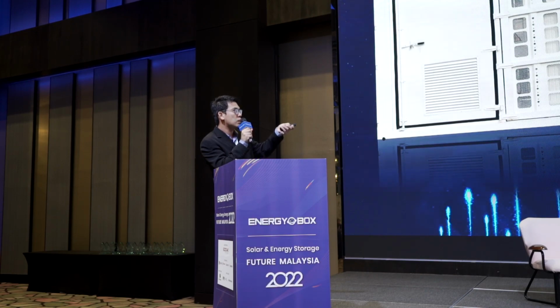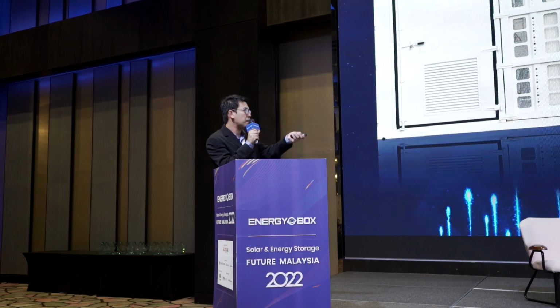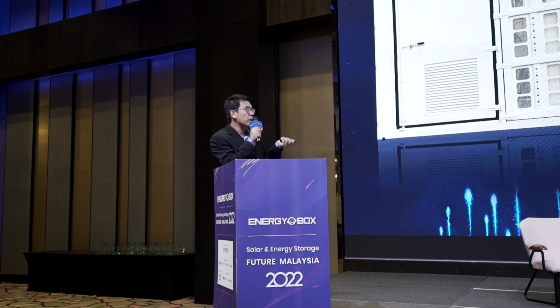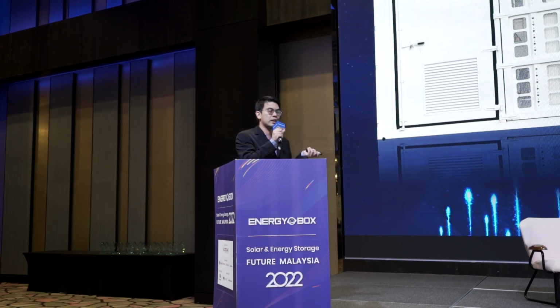Your local team will only need to install this box and connect the wires. It's really plug and play. The fiber optic cable can come through from below and be connected to our data logger. We support voltage up to 33 kV. Transformer capacity is up to 6.75 MVA or 7,000 kVA. We provide a ring main unit, and everything is packed within a standard 20-foot container with IP56 rating, and it can be easily installed and used outdoors.